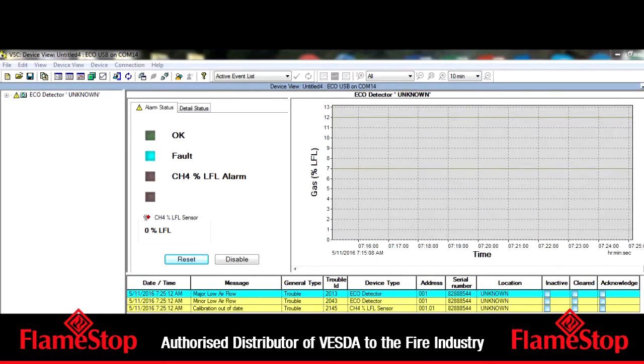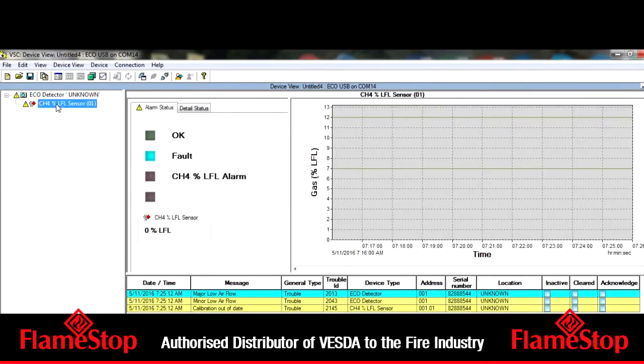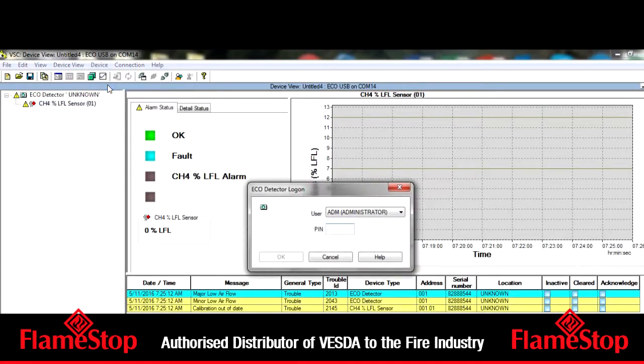With the zero gas running, go to the upper left-hand corner and expand the tree. Highlight the sensor, then go to Device, then click on Zero Calibrate. Enter the password 0999, then click OK.